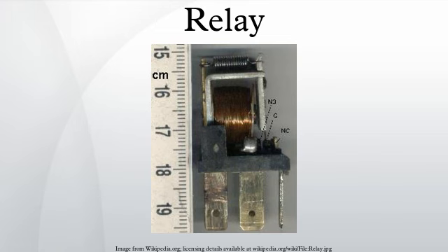Coil voltage: machine tool relays usually 24 VDC, 120 or 250 VAC; relays for switchgear may have 125 V or 250 VDC coils. Sensitive relays operate on a few milliamperes. Coil current, including minimum current required to operate reliably and minimum current to hold.